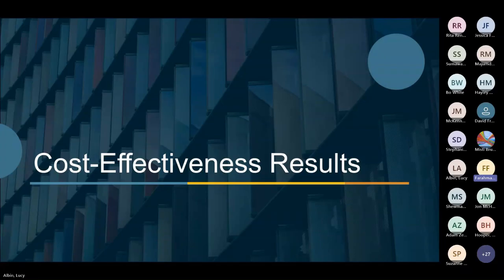In short, we examined all of those, and this will be documented in the report. We did not find conclusive evidence that that's going to be the case. We generally found that the heating capacity was lower than the cooling capacity in nearly all cases when we looked statewide for these particular building types and for this mechanical equipment. We also found that strip heating and defrost are most likely to occur in the middle of the night, in that early morning when the building is not occupied. So running that heat pump in reverse a little longer to defrost the coil would not lead to comfort impacts, while effectively defrosting the coil without needing that extra electrical capacity.